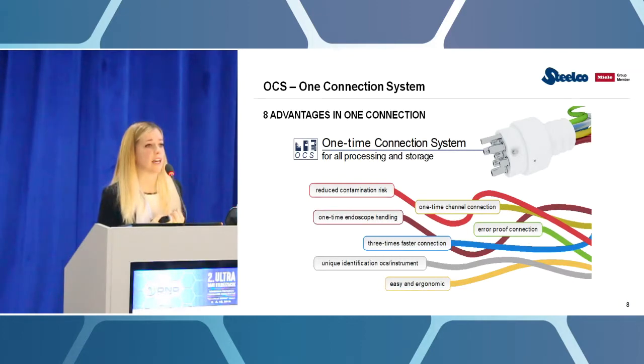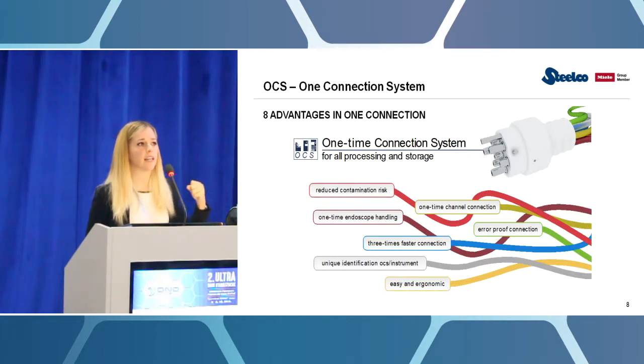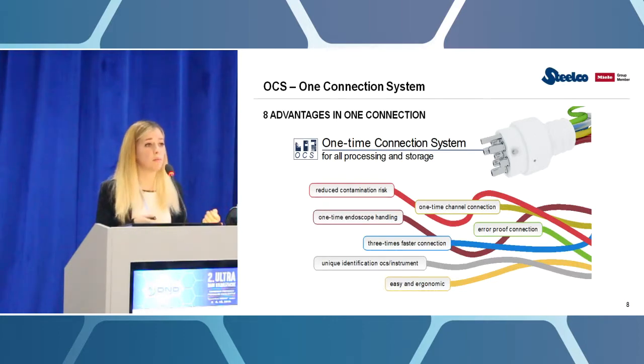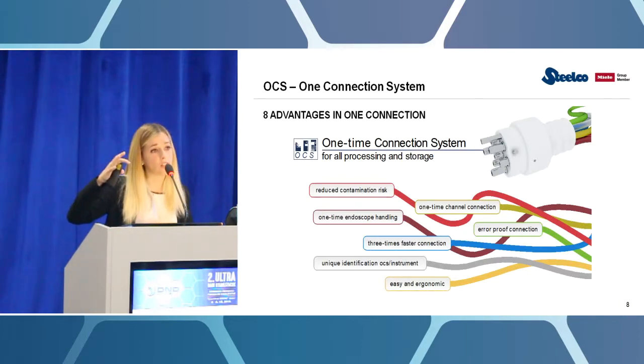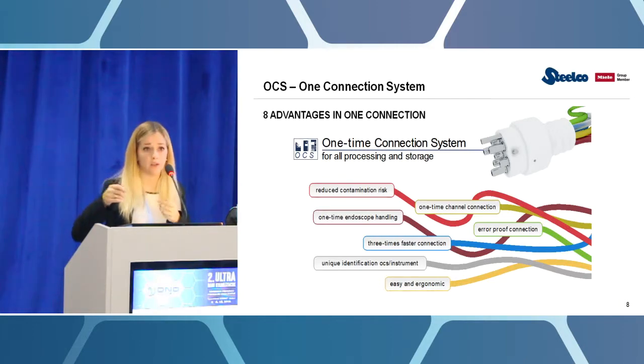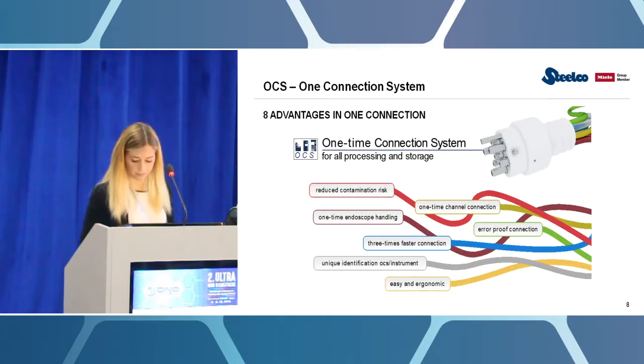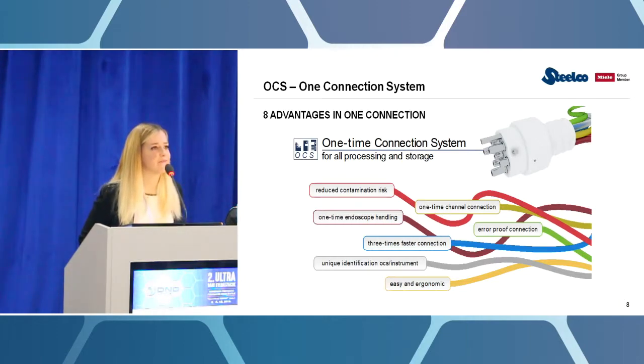But the greatest benefit of this system is that you're not touching the endoscope anymore. You're not manipulating the endoscope, and you know how critical these scopes and these instruments are. So it's very easy to damage them, and it costs a fortune to repair endoscopes. So what we wanted to improve was also this dimension. Using these systems, you're basically decreasing the rate of manipulation of endoscopes, because you're moving from one stage to the other just with your mesh tray and the OCS attached to the endoscope without having to touch the endoscope anymore. Do you like it? Yeah.